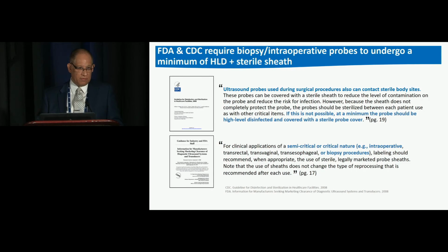So here are two very, very important documents, one from the CDC and the other from the FDA, which directly address the use of these kinds of probes. Let me read them briefly to you. The CDC says the following: ultrasound probes used during surgical procedures can also contact sterile body sites. These probes can be covered with a sterile sheath to reduce the level of contamination on the probe and reduce the risk for infection. However, because the sheath does not completely protect, the probe should be sterilized between each patient use, as with other critical items.